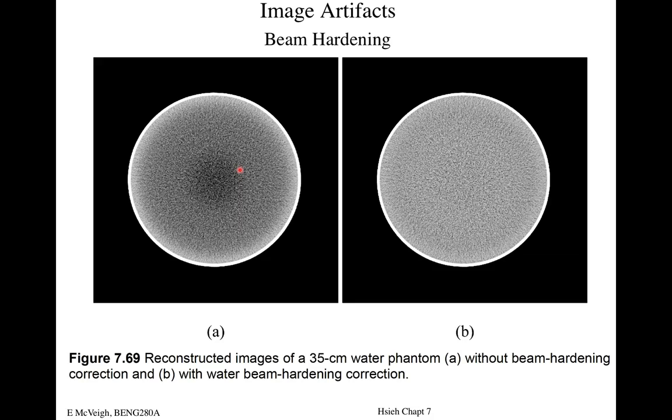do a back projection reconstruction and look at your results, you'll have a kind of a hole in the middle of your phantom, right? And this hole is because for these central pixels, there's no way a beam hit these pixels without penetrating through a lot of phantom first, right?